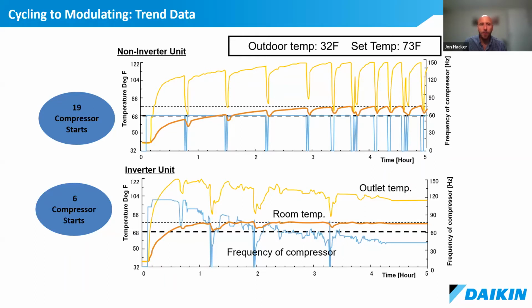So looking at the non-inverter unit, I think the first thing we need to call out is that the frequency of the compressor is either operating at 0 or 60 hertz. It's either on or it's off. I think that's abundantly clear. What we see over this 4-hour period is that the compressor for the non-inverter unit turns on and off 19 times. The other thing that we'll see is that when the equipment is on, it will try to satisfy the set point, and then it will cycle off. And when it cycles off, the room temperature, that orange line, will deviate significantly from the set point, which is shown as the smaller dashed line for this example at 73 degrees Fahrenheit.